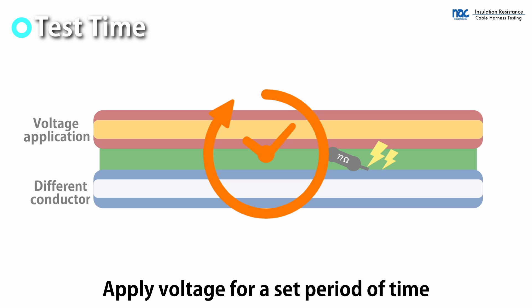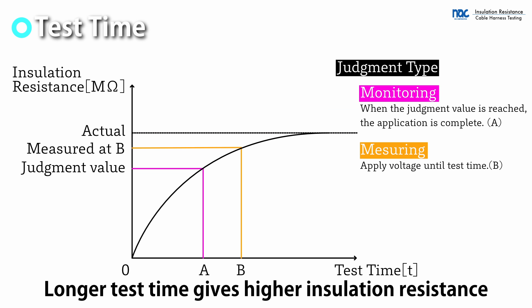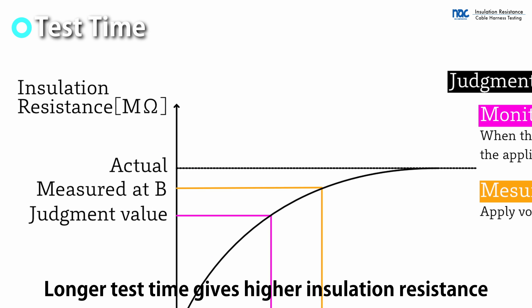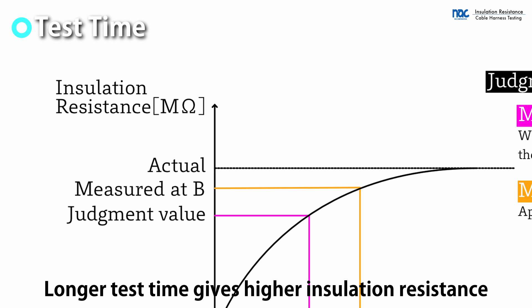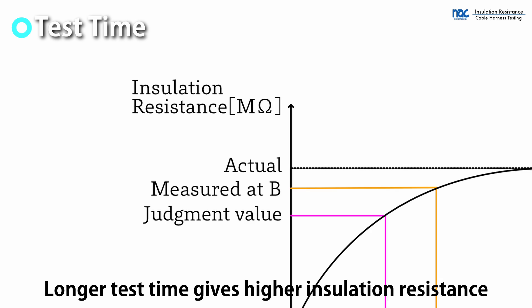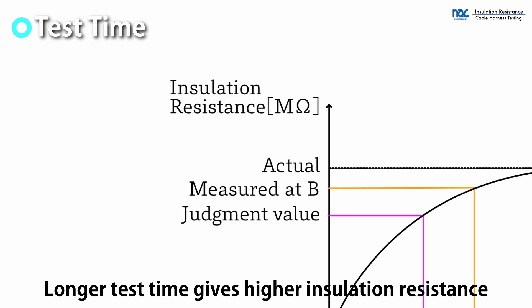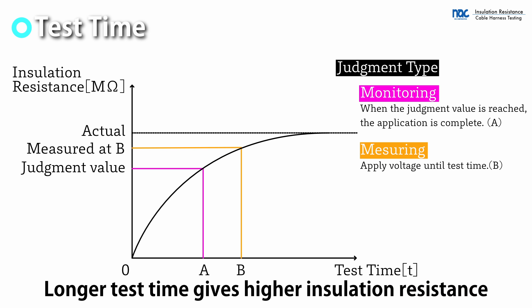Set the time per application. The longer the time, the more electrical load is applied to the test target. In insulation testing, however, a longer test time is advantageous. This is because it takes time for the insulation resistance to reach an equilibrium state. By applying the load for a certain period of time, the insulation resistance of the test target can be measured.